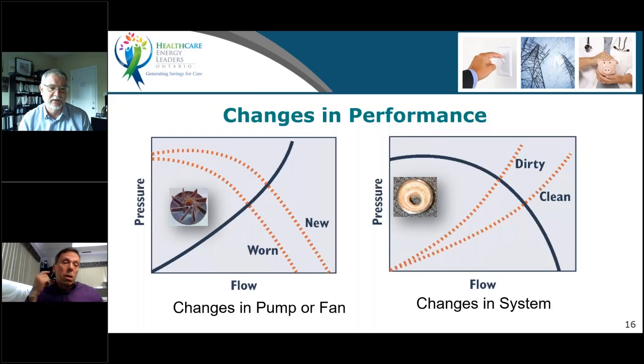pressure flow characteristic. And if you have a cooling tower, that's the pump you should be listening to in terms of cavitation. They're usually the ones that have more problems with cavitation because they're open systems. So cooling tower pumps, listen to them. If you think you hear sand going through it, it's probably cavitation. Cavitation, absolutely.